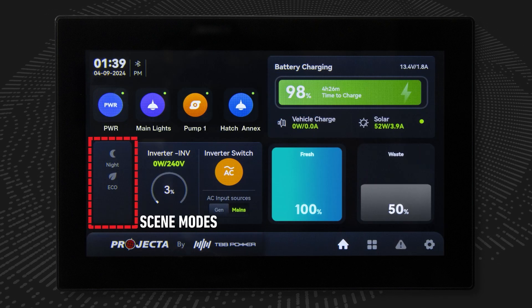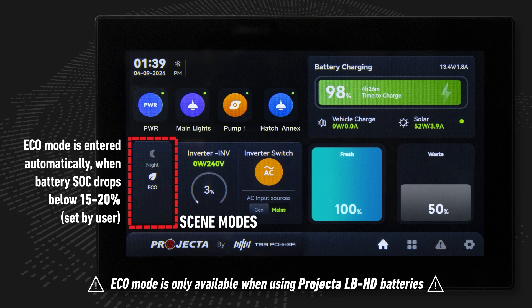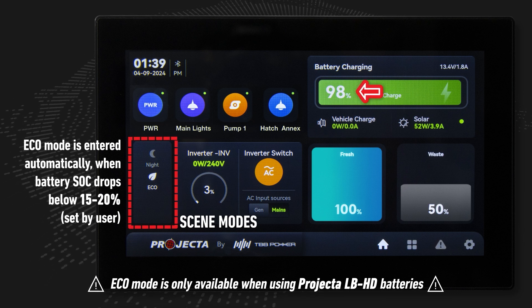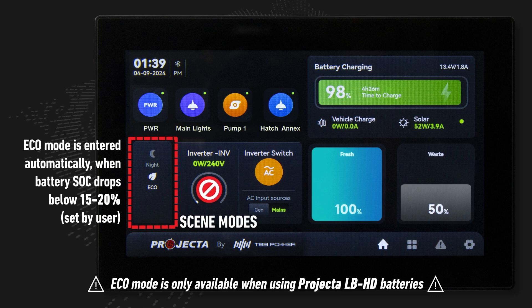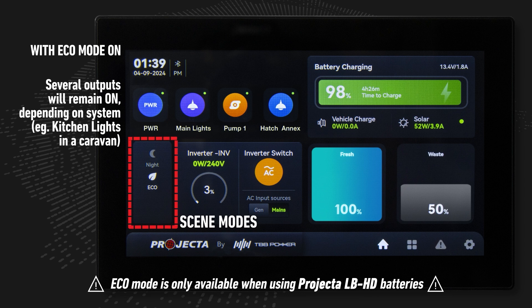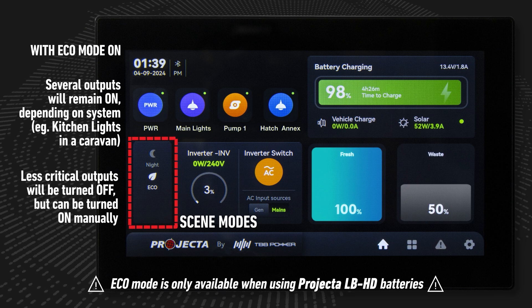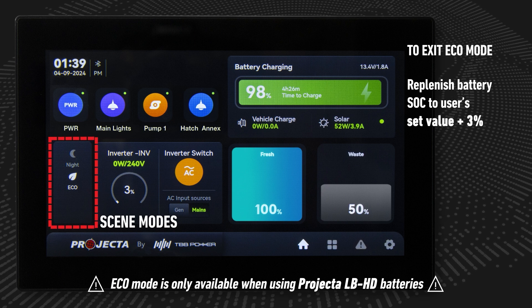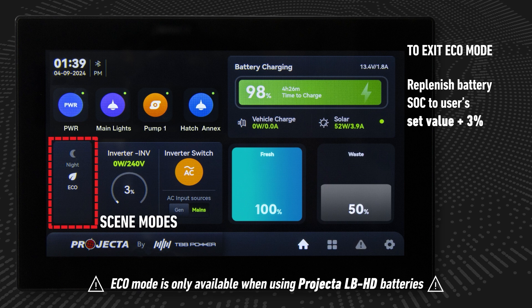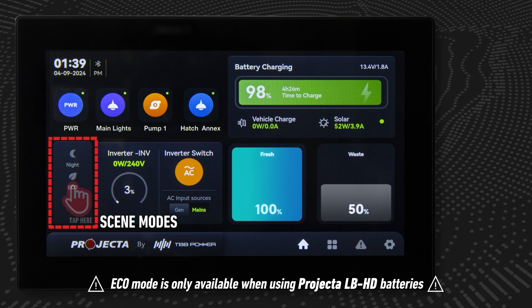This region provides two scene modes: eco mode and night mode. When eco mode is engaged, the IntelliGrid Compact System will enter eco mode automatically once the battery SOC drops to a certain percentage — this percentage can be set by the user to a value between 15% and 20%. When eco mode is entered, the system will shut down all inverter outputs and heavy loads, keeping only essential loads on. In most cases several outputs will remain on, though these differ based on the application. Circuits for less critical outputs will be turned off, and these can be turned on again manually. When battery SOC returns to the user's set value of between 15% and 20% plus another 3%, the system will automatically exit eco mode. Eco mode will also be exited if the system is connected to AC grid charging or if the user manually exits this mode.